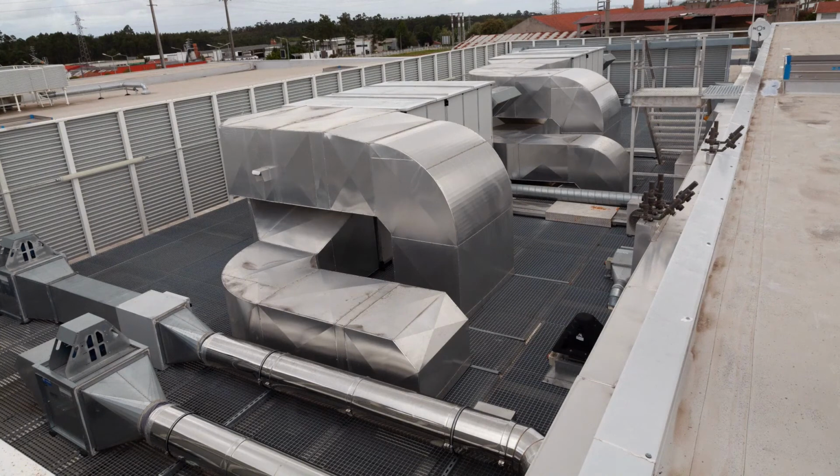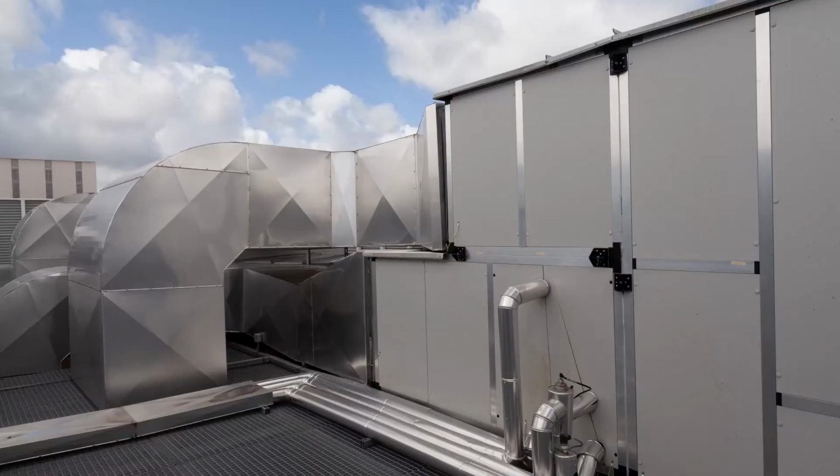And here we see the air handling units. There are 2 independent units maintaining the air temperature and comfort inside the shop, and these units are not activated with a liquid flow or an indirect system. They are directly connected to the refrigeration system, meaning the CO2 is either cooling or heating up the air which is supplied into the shop. So this DX evaporator and the gas cooler is connected to the air handling unit.